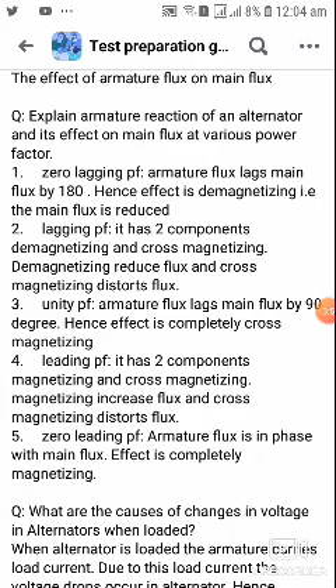Number 2. Lagging power factor. It has two components, demagnetizing and cross magnetizing. Demagnetizing reduces flux and cross magnetizing distorts flux. Number 3. Unity power factor. Armature flux lags main flux by 90 degrees, hence its effect is completely cross magnetizing.